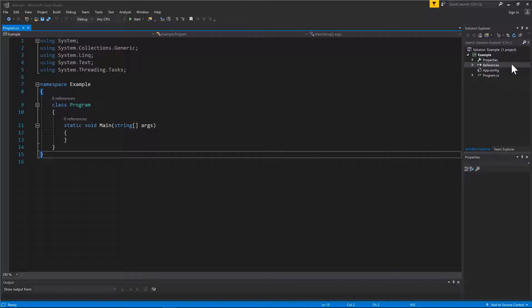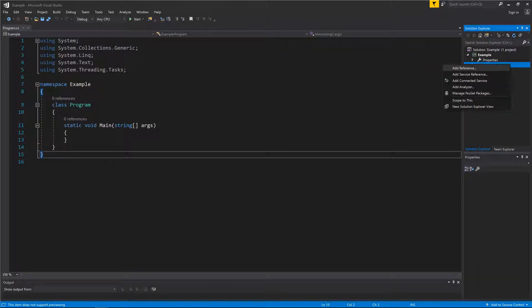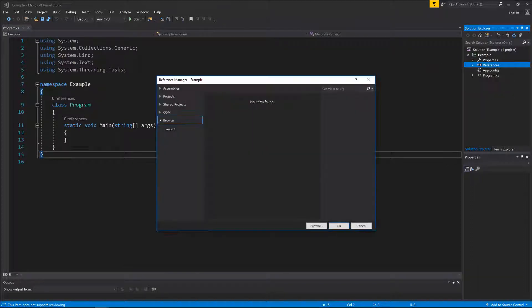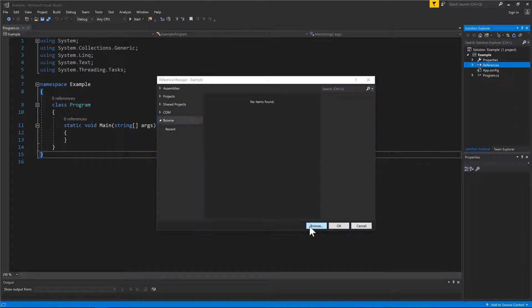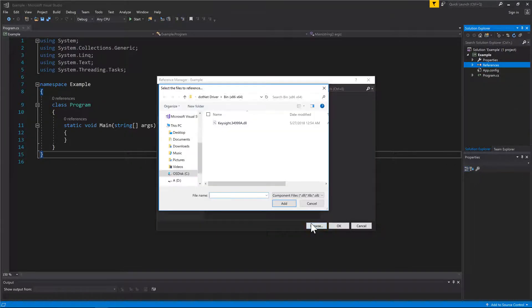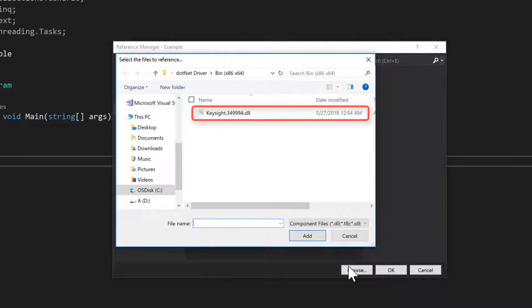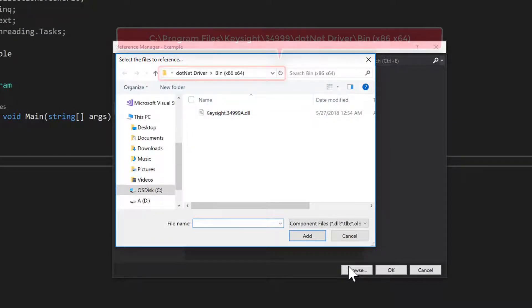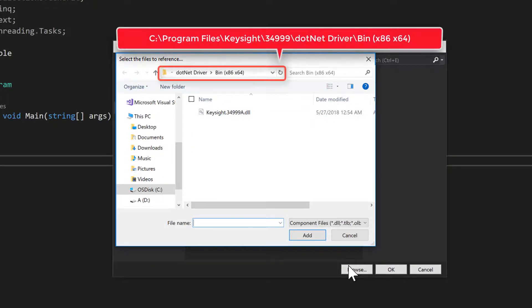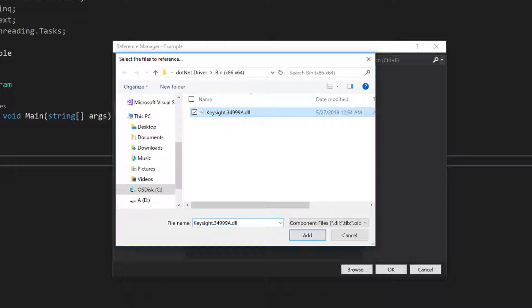To add a DLL reference, right-click the Reference tab and select Add Reference. In the pop-up window, go to the Browse tab and click the Browse button. Then look for the Keysight.34999A.dll file. By default, the DLL is in the folder as shown on the screen. Select the DLL and click Add.